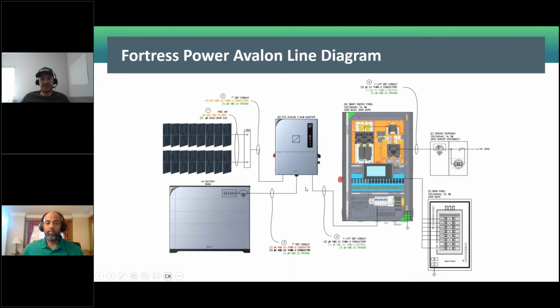But a lot of the special sauce is going to come down here in the breakers, or the relays, I'm sorry. Just right below the screen there, you'll see these relays, and you can set up automatic load shedding, so that when your sales rep goes in and promises a full home backup experience, they're not completely lying. They are having full home backup with smart load management. And so the heavy loads, the water heater, the HVAC, the heavy loads that the system may or may not run during that power outage, depending on how they size it, will automatically shed during that power outage situation.